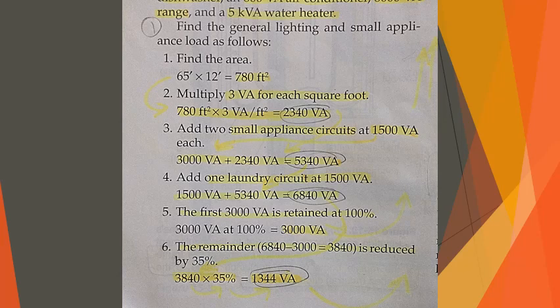Here's an example of how to apply these rules for a mobile home. Find the total electrical load for a 65-foot by 12-foot mobile home. It has 2 small appliance circuits, a laundry circuit, a 2500 VA space heater, a 100 VA fan, a 500 VA dishwasher, an 800 VA air conditioner, an 8,000 VA range, and a 5 kVA water heater.